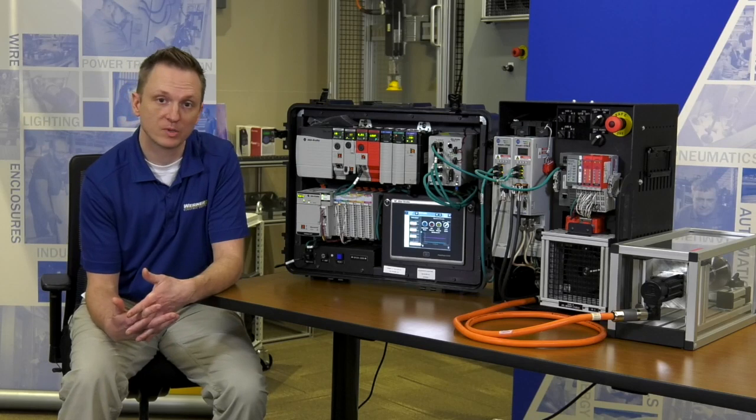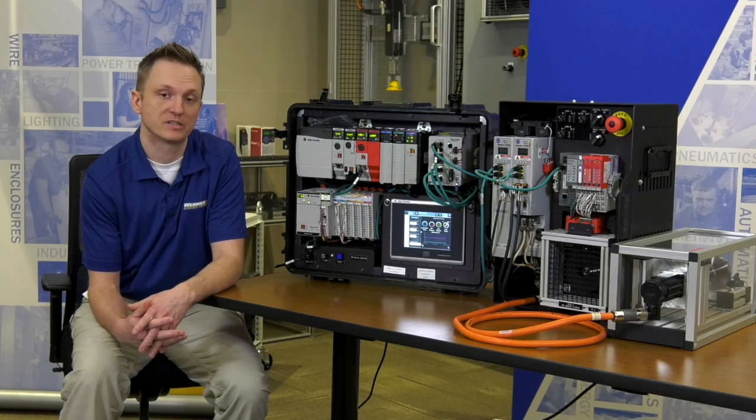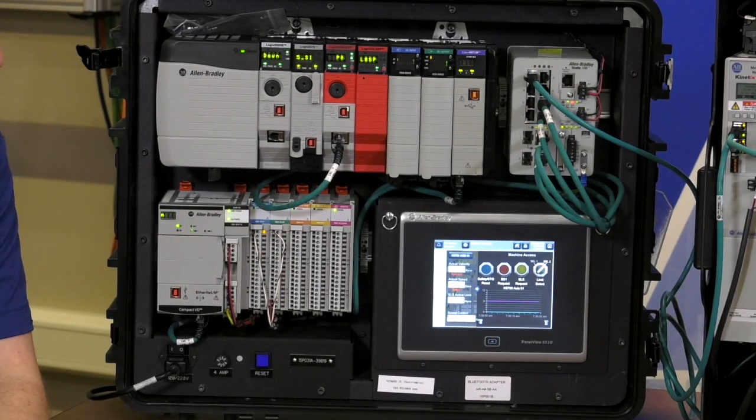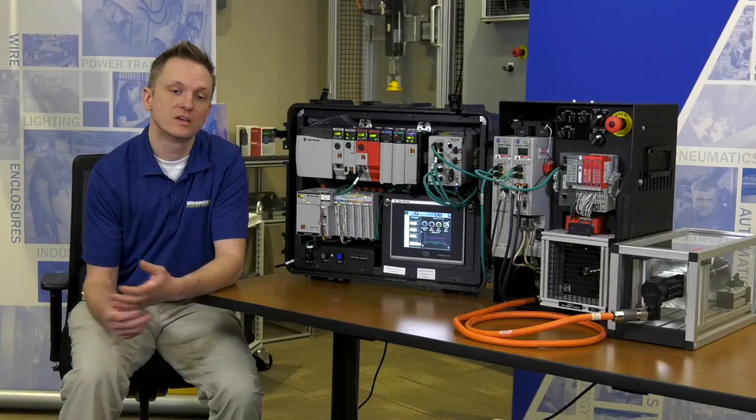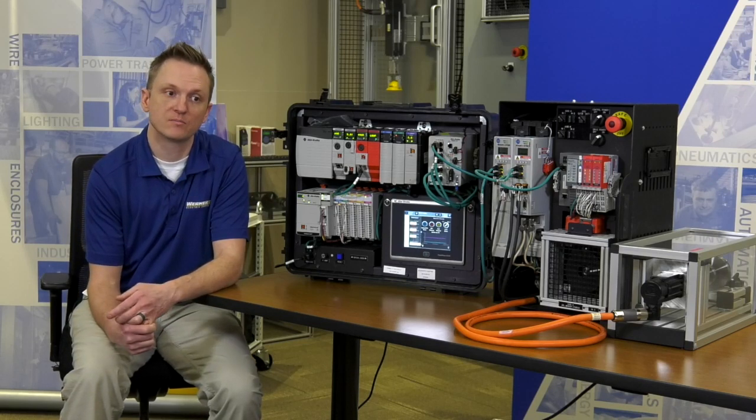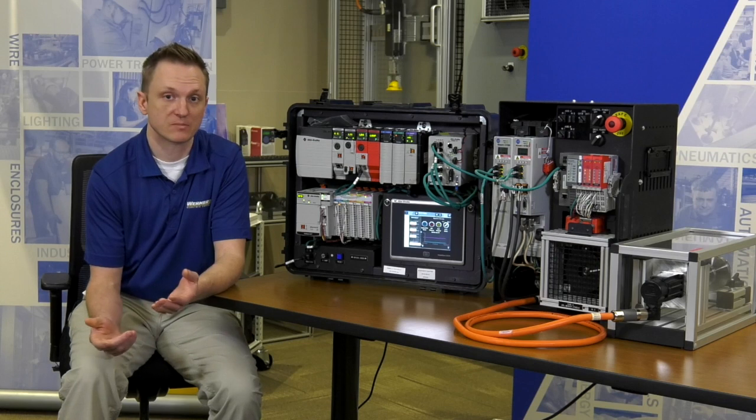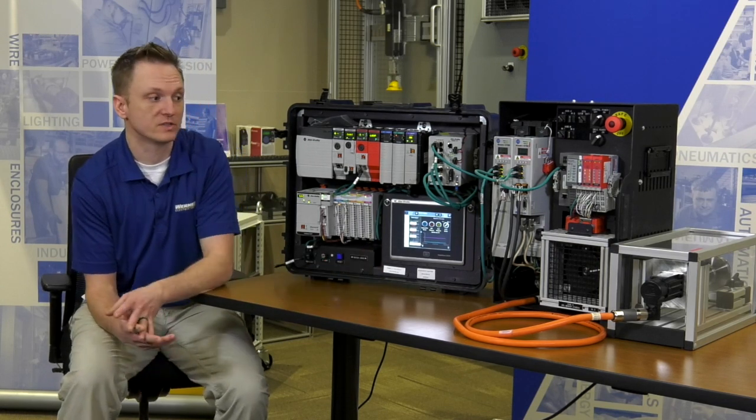The two features I'm going to be talking about today are the SS1, SafeStop 1 feature, and then the Safe Limited Speed. Those aren't the only features that are available on the Kinetix 5700 ERS4. You're able to do Safe Limited Positions, Safe Limited Direction, Safe Operational Stop, Safe Brake Control, Safe Stop 2. But I'm not going to be talking about the rest of those. I'm just going to be doing these two features.